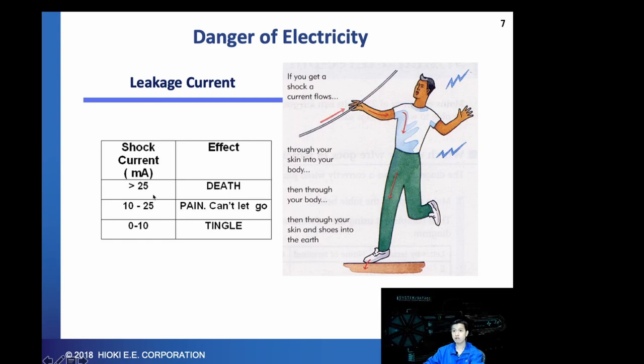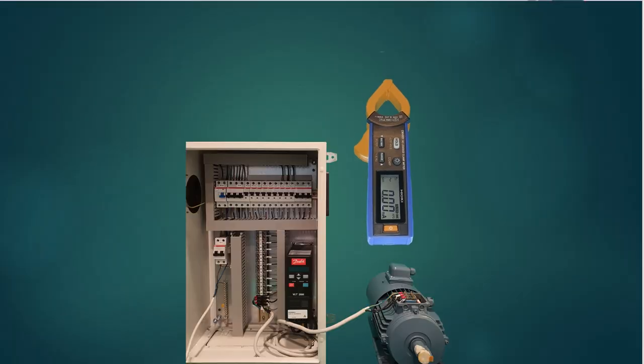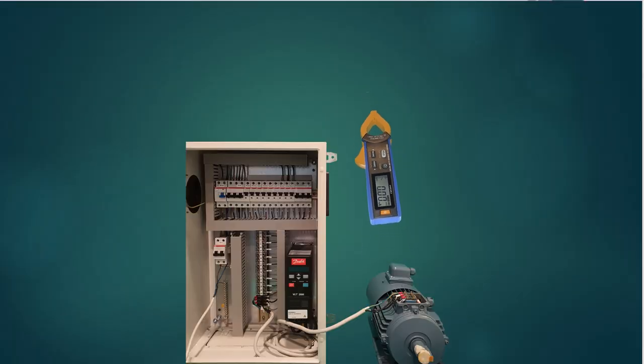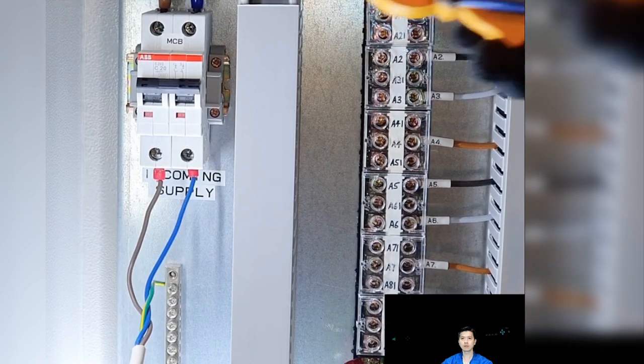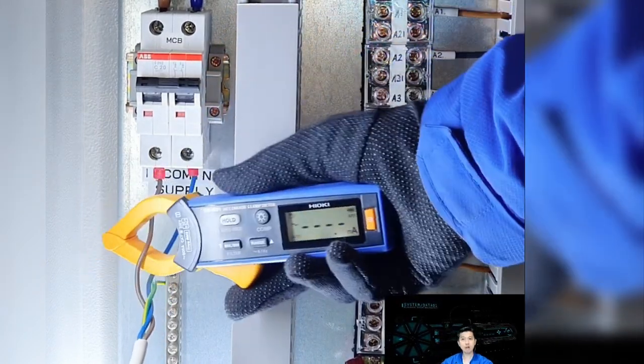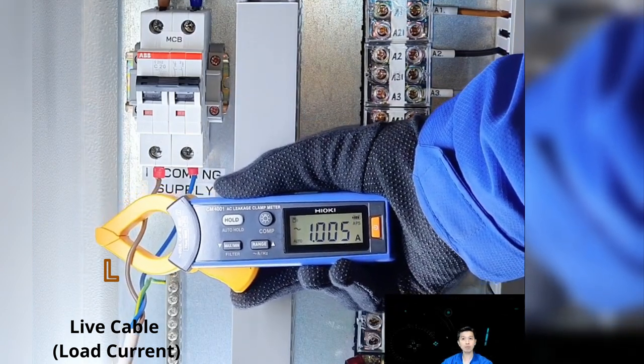Now, with that short background on leakage current, I shall explain how to measure leakage current with the CM4001. For the demonstration example, we will be using this distribution board which is powering the VSD model. With the CM4001, we will use it to measure the live, live and neutral, and also the earth cable. In the first example, you can see how we can measure the load current of 1A by clamping on the live cable.